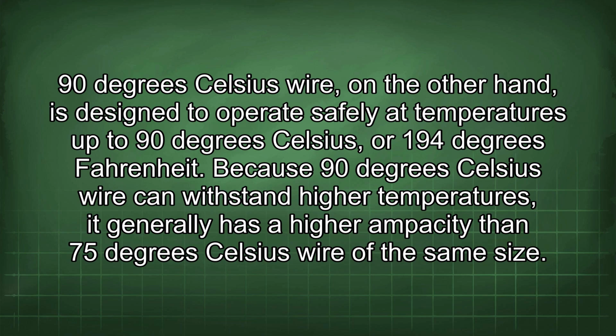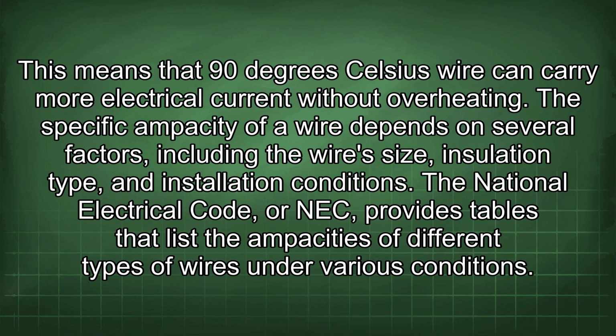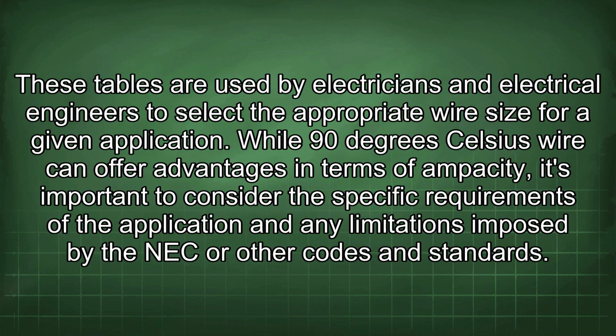Because 90 degrees Celsius wire can withstand higher temperatures, it generally has a higher ampacity than 75 degrees Celsius wire of the same size. This means that 90 degrees Celsius wire can carry more electrical current without overheating. The specific ampacity of a wire depends on several factors, including the wire's size, insulation type, and installation conditions. The National Electrical Code, or NEC, provides tables that list the ampacities of different types of wires under various conditions. These tables are used by electricians and electrical engineers to select the appropriate wire size for a given application.